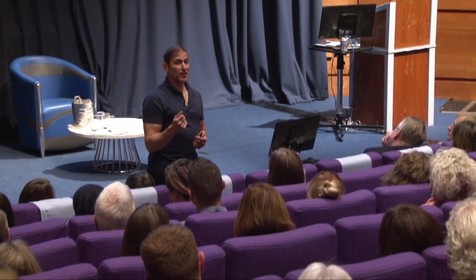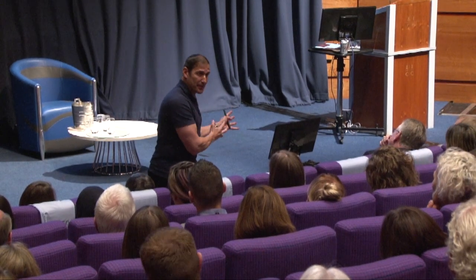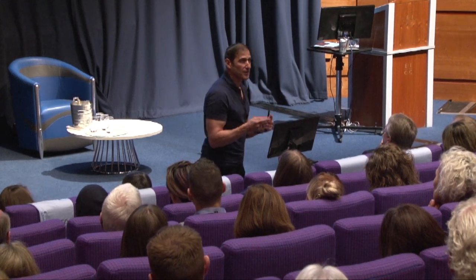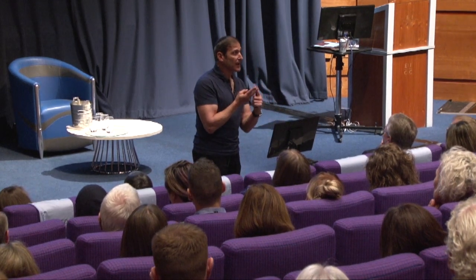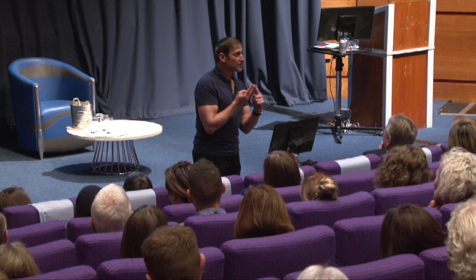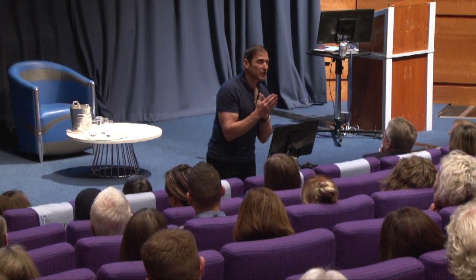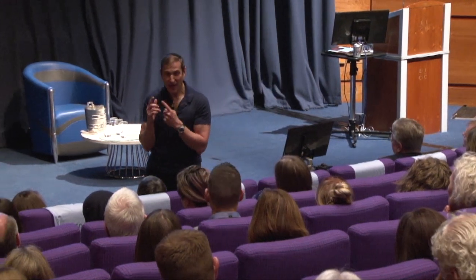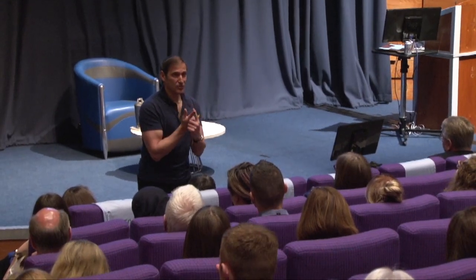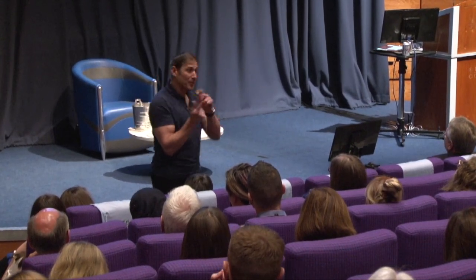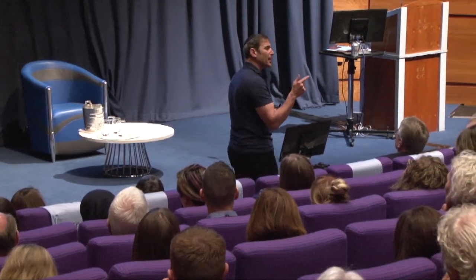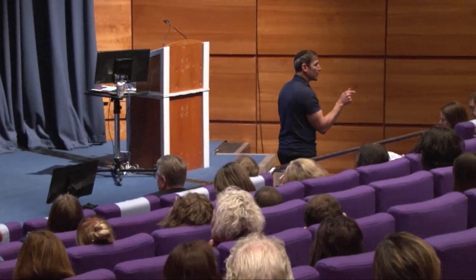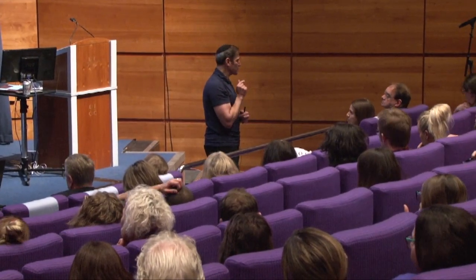So what do I need to know? Forget the app. To decide, can I safely scan this patient? What do I need to know? Gender, height, weight, magnet, which hardware, what field strength, what coils are transmitting, how did you position, and where did you center? I'm going to take all of that and I'm going to apply it to your knowledge of the implant or implants that this patient has on or in them, and I'm going to finally make a safety risk assessment.